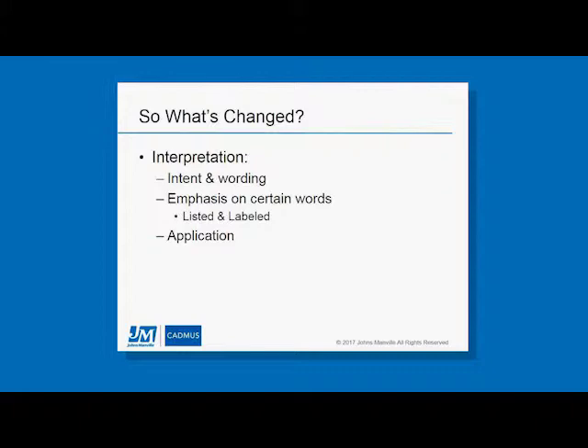The emphasis is on the words listed and labeled within the code, which is becoming more specific as far as the material application. And then as far as the application, is it going to be something that requires a fire-hour rated construction, or can those combustible pipes and surfaces within a plenum be insulated with a material that's just 25/50 rated, that's listed and labeled for that application?